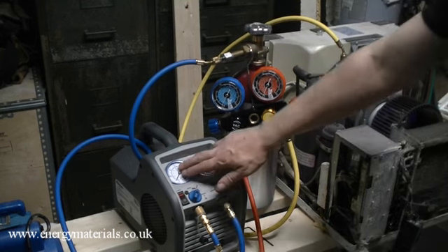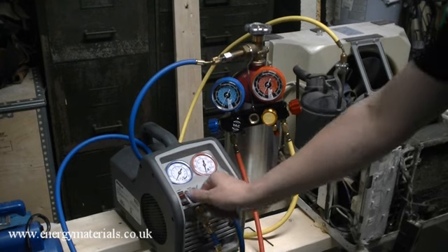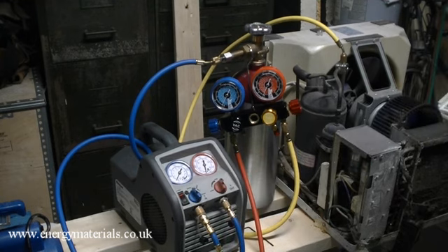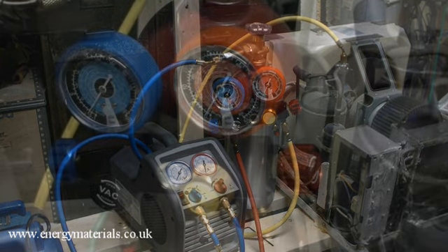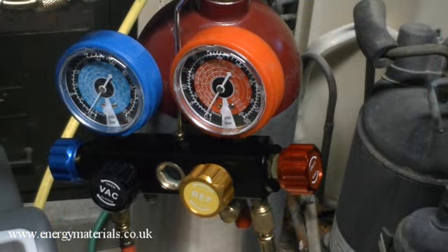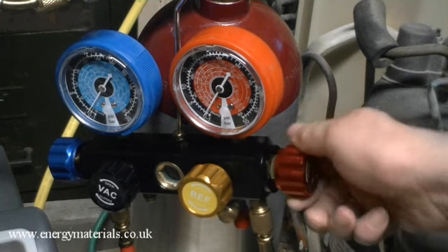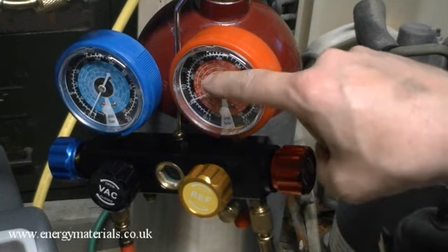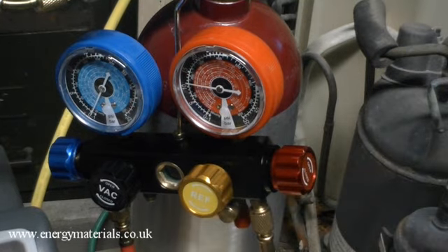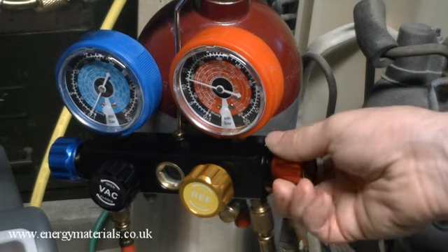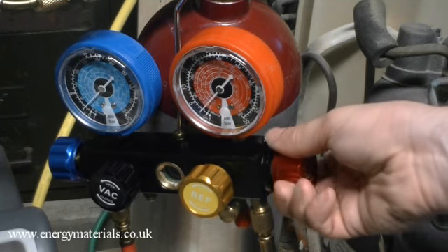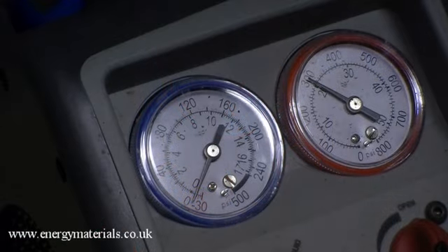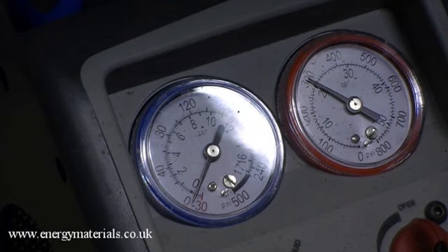And we can monitor the pressures on the inlet side and the outlet side. I think it's fair I can increase the rate. Now we wait. I'm going to open this a little bit more. No, that's it. So just a test to see if refrigerant is still being released. If I close this valve, yeah, you can see the pressure increasing as refrigerant is coming out into our gauge set. Let's open it up again and continue the transfer. And now with a negative pressure on the inlet, let's have a look at our gauges.